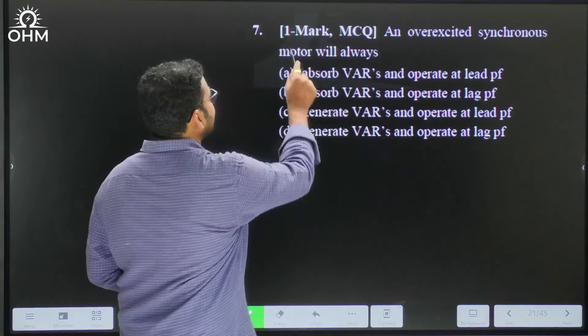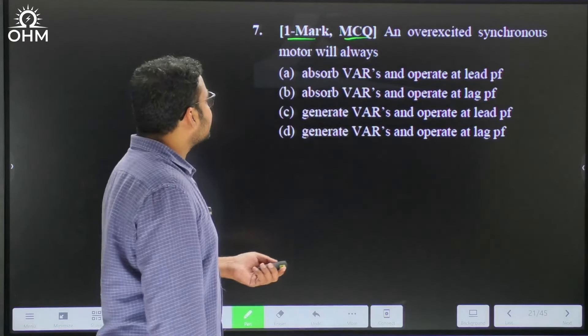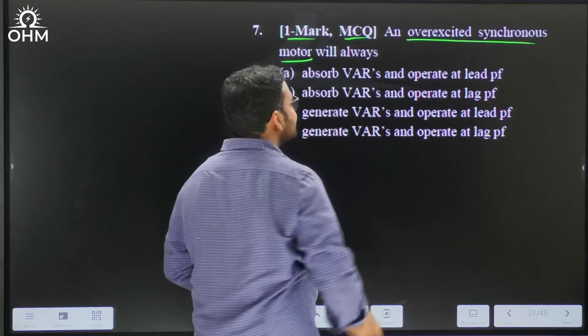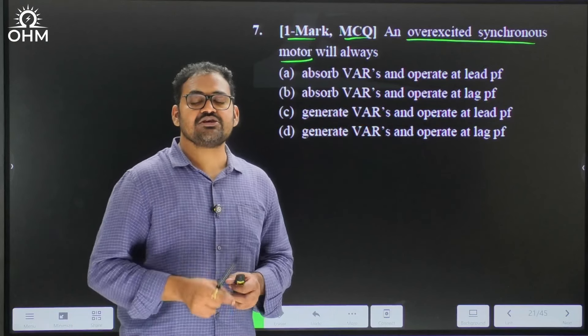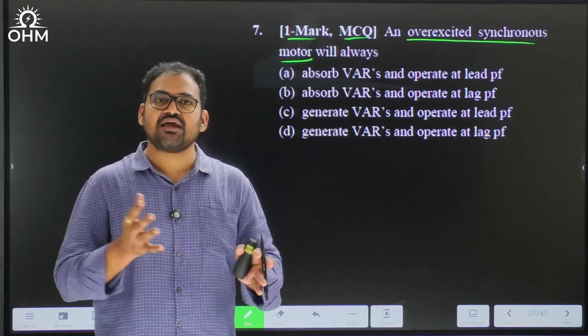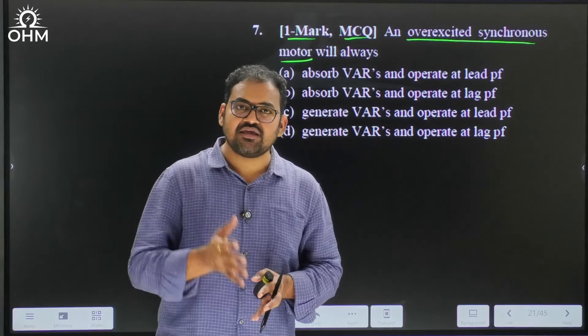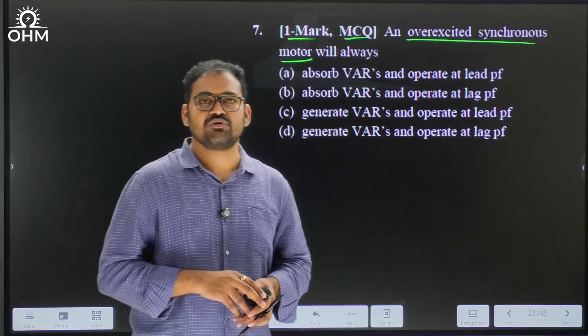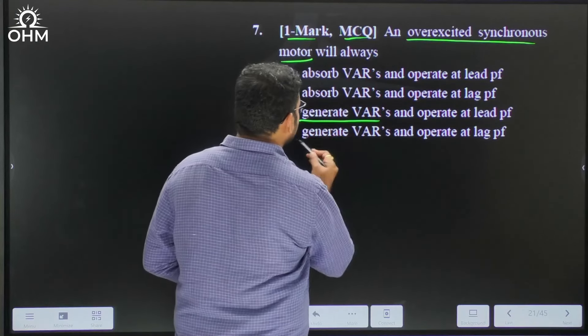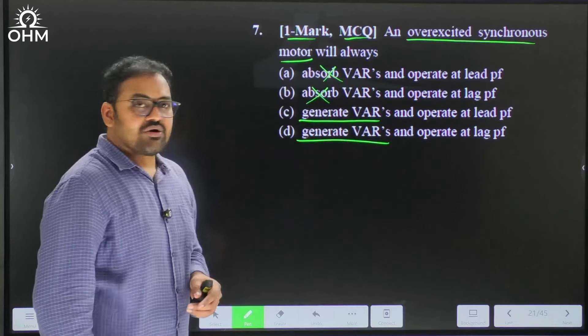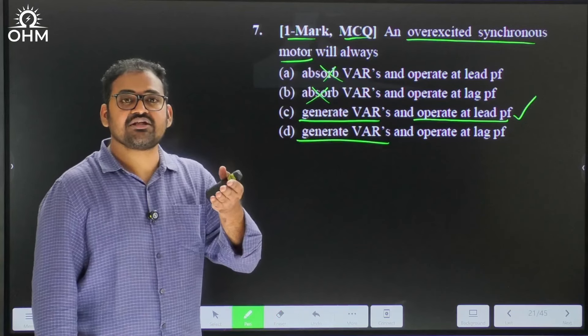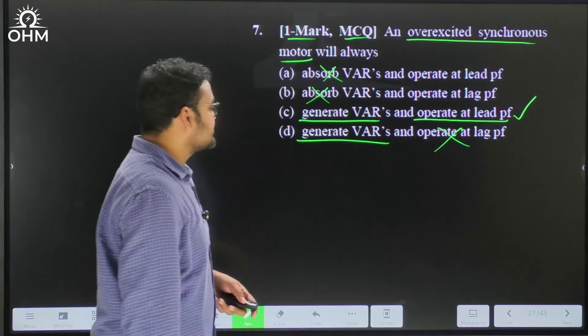Let us move to the next one-mark multiple choice question. An overexcited synchronous motor will always — this is a straightforward facts-based question. An overexcited synchronous motor is also known as a synchronous condenser. It generates reactive power so that the power factor of lagging load circuits can be improved. It operates at a leading power factor — like a capacitor generating reactive power. Therefore the correct answer is option C.